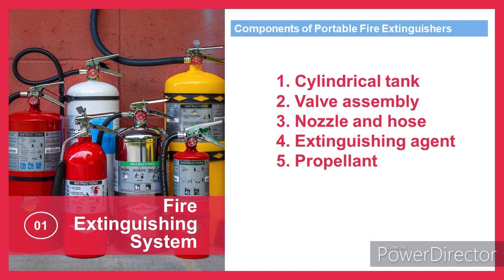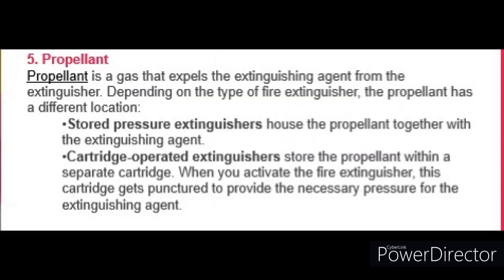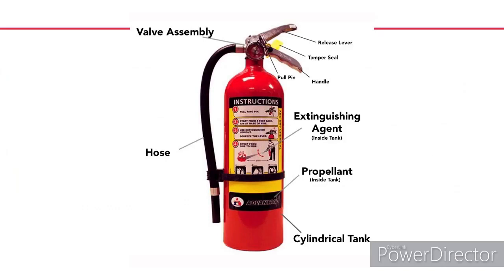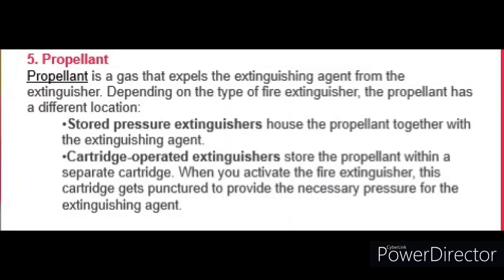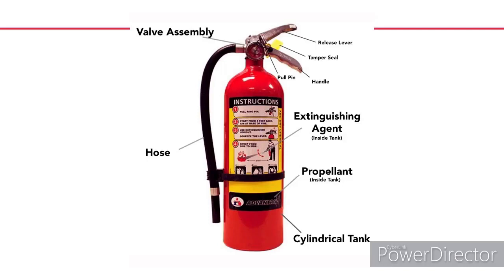Another component is the propellant. Propellant is a gas that expels the extinguishing agent from the extinguisher. Depending on the type of fire extinguisher, the propellant has a different location. First, the stored pressure extinguishers house the propellant together with the extinguishing agent. Second, the cartridge-operated extinguishers store the propellant within a separate cartridge. When you activate the fire extinguisher, this cartridge gets punctured to provide the necessary pressure for the extinguishing agent. Here is a sample photo to show fire extinguisher components.